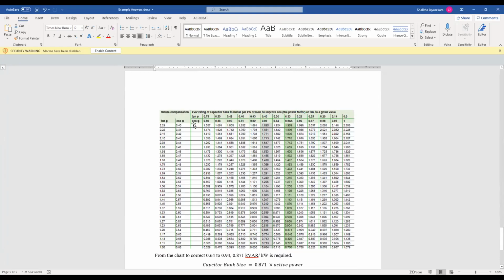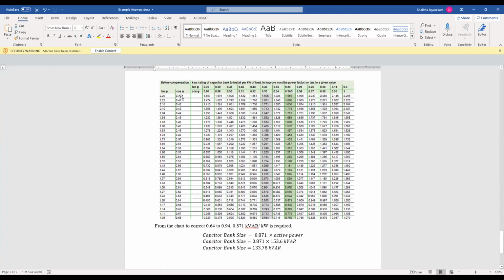So what you are going to do is check the row for the before compensation value. Before compensation means the current value. So it is 0.64, right? Here is 0.64, and you need to upgrade it to 0.94. So here we have 0.94. We go through this row and come through this column, and you will find the compensation value as 0.871.